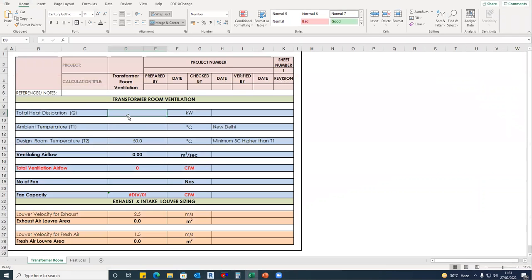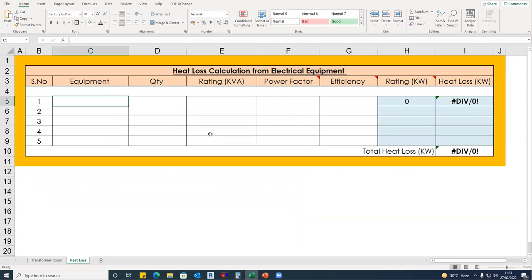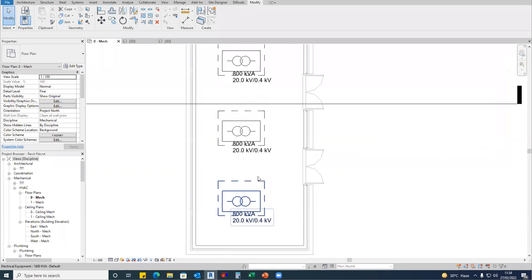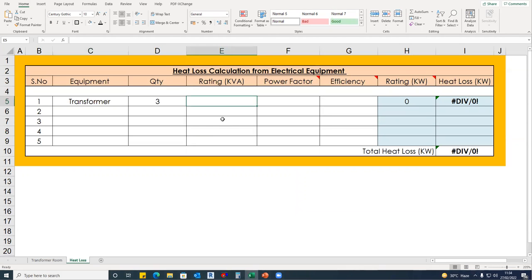So first thing, to start the calculation, you need the total heat dissipation. How much, मतलब heat को कितना dissipate कर रहा है वो, तीनों जो transformers हैं, तो तीनों में से कितना heat space में dissipate हो रहा है, reject हो रहा है. तो एक Excel sheet है, ठीक है, based on whatever your electrical equipment is, you can use this Excel sheet to calculate the heat loss, okay, heat rejection from that electrical equipment. So that electrical equipment in our case is transformer. Transformer quantity is 3. What is the rating? I'll go to the drawing. It is 800 kVA.